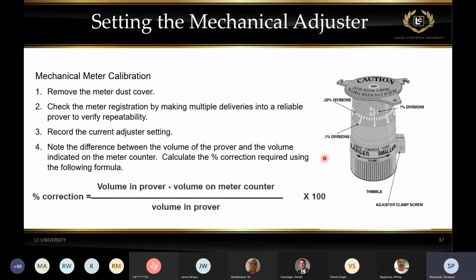Well, it starts with the process of calibration. And again, we'll use the example of a prover. So we would normally remove the cover, expose the adjuster, and we'll make deliveries to the prover. We'll probably make more than one delivery. Normally, the first delivery is called wet down. You discard that delivery and then make a number of deliveries to check for repeatability. If repeatability is there and you are off, we can now calculate how far off we are.